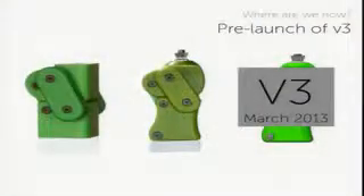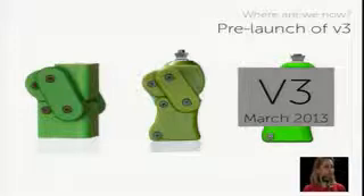Shortly after the project came into DREV, we did a second iteration. You can see there's a noise dampener — it's a little quieter. The curvature has also changed. Another feature we learned from version 2, tested in Ecuador, was that it takes a lot of energy to bring the leg forward, so we added a spring to help. One lesson from that iteration was that it was too big — one user said, politely, 'maybe that's fine for you Westerners.' That resulted in version 3, which has a much slimmer profile, and we really tried to design it aesthetically beautiful — something people are proud of.